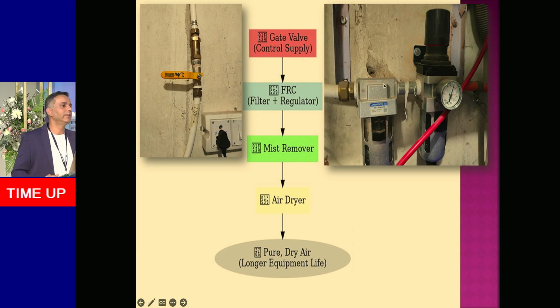Then you need to have an FRC in the pipeline. This is very important - that's a filter regulator, so it filters the dust particles coming in the compressed air, and at the same time regulates the amount of pressure needed for your dental chairs. Don't have high pressures.